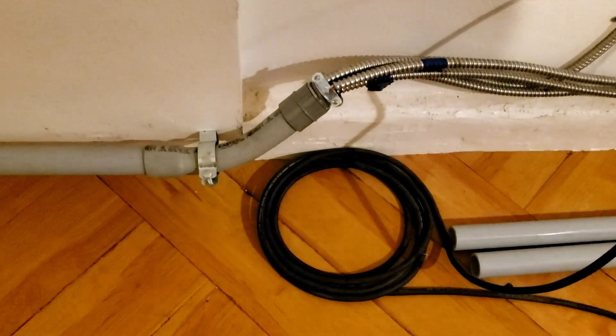It was the next wire down in line that went with this circuit breaker. I pulled it all out and got it out of the way. You can see all the wire on the floor that was in the pipe before. I straightened it out on the tip as best I could so it wouldn't give resistance going down. It took some tugging, and I pulled the whole thing over a bit, but I can straighten that back out and fix it - not an issue. Now I'm going to rework this side corner.